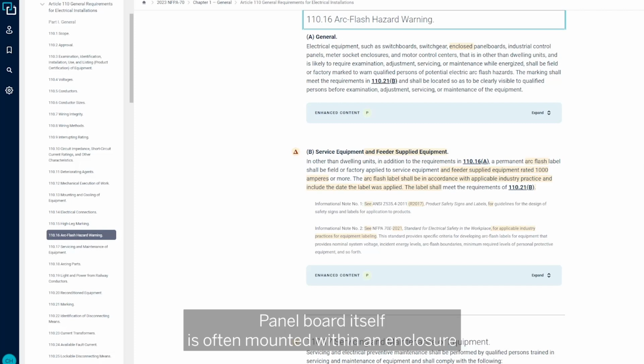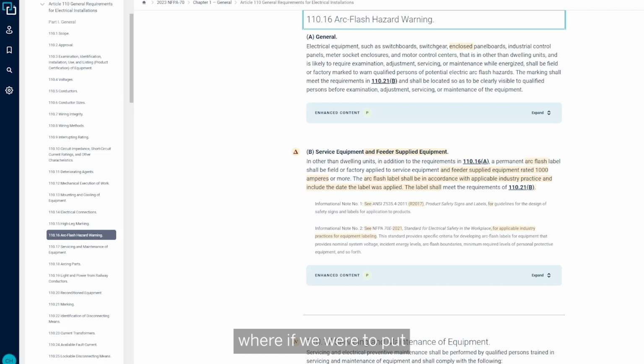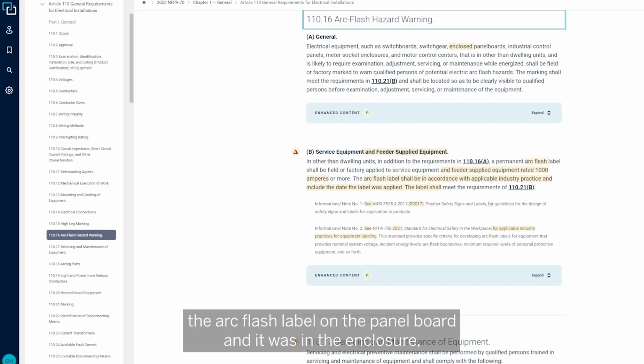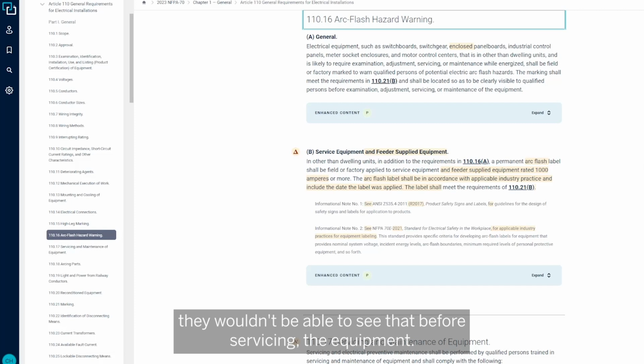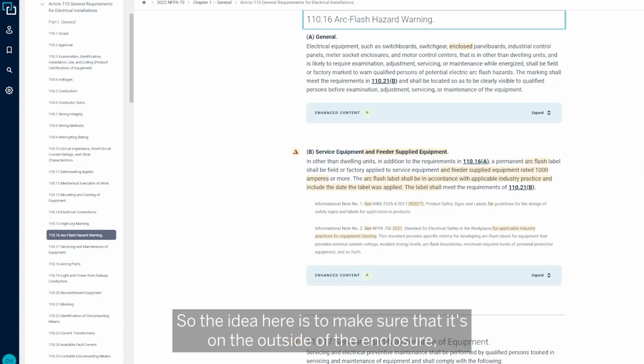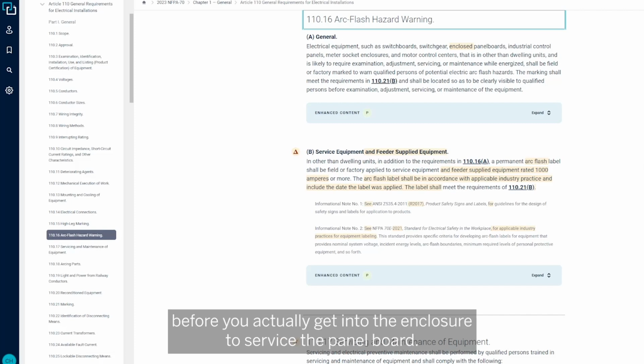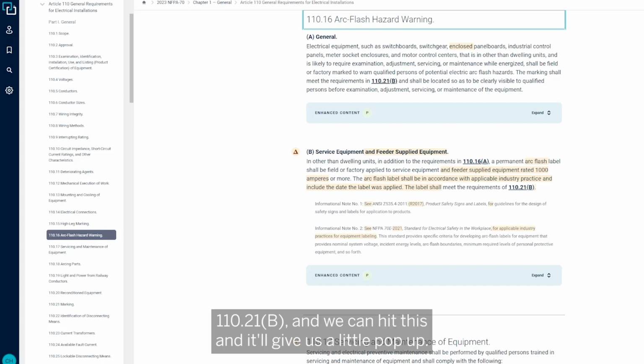Well, a panelboard itself is often mounted within an enclosure where if we were to put the arc flash label on the panelboard and it was in the enclosure, they wouldn't be able to see that before servicing the equipment. So the idea here is to make sure that it's on the outside of the enclosure before you actually get into the enclosure to service the panelboard.